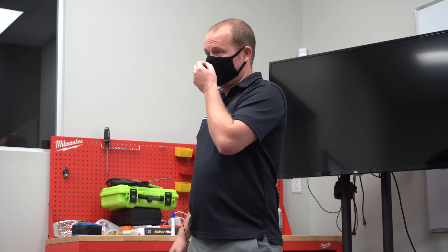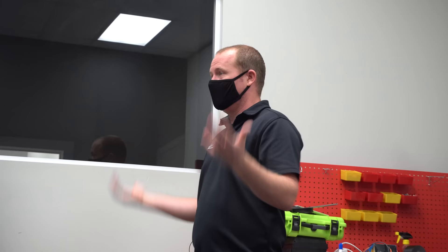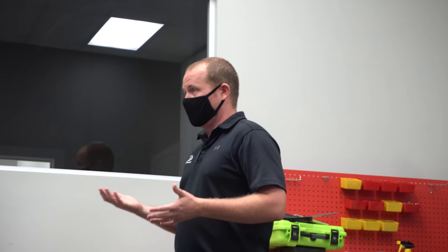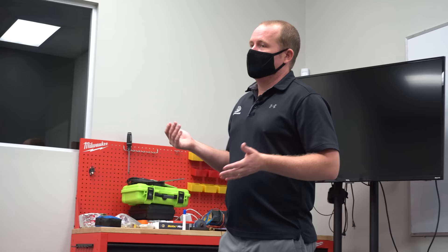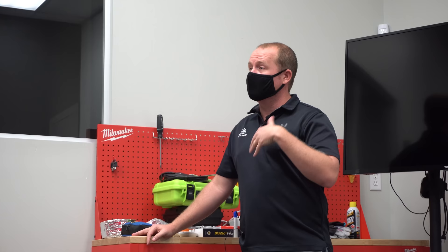Let's go to the supply plenum. Because a lot of our units are in unconditioned areas, sometimes you'll get a little bit of growth on the outside of the air handler cabinet and the supply plenum. Ideally they'd be so well sealed and insulated that you'd never get growth. If it's minor, just clean it. You can use a chlorine solution, or Evap Plus on a rag will often do a good enough job to wipe it off. If it gets severe and appears to be due to a poorly sealed or poorly built plenum, that's something we need to quote to redo.